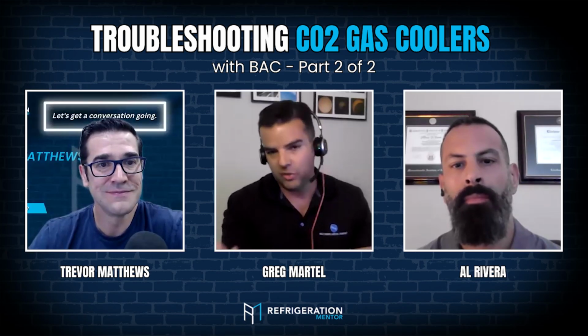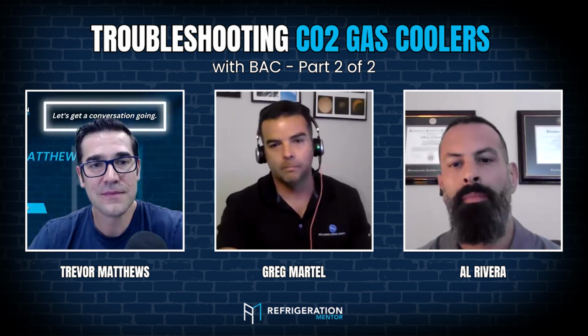If you have a new unit and no matter what voltage you send to the fans, they still run at full speed, it's most likely, 90% likely, that it's just set up incorrectly. Great for the summertime, not good in the wintertime.